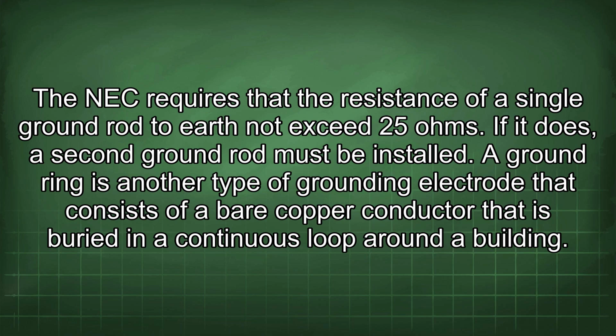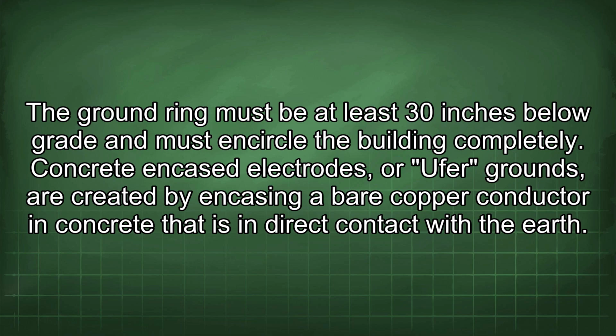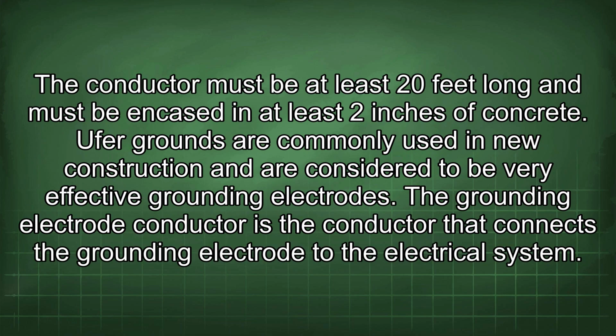A ground ring is another type of grounding electrode that consists of a bare copper conductor that is buried in a continuous loop around a building. The ground ring must be at least 30 inches below grade and must encircle the building completely. Concrete encased electrodes, or UFER grounds, are created by encasing a bare copper conductor in concrete that is in direct contact with the earth. The conductor must be at least 20 feet long and must be encased in at least 2 inches of concrete. UFER grounds are commonly used in new construction and are considered to be very effective grounding electrodes.